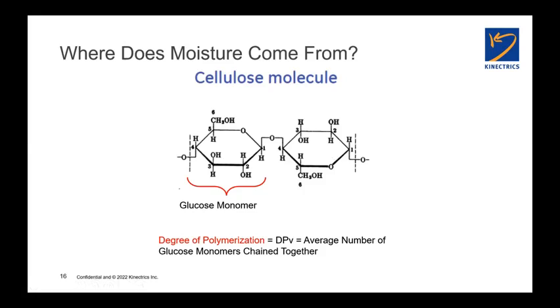And cellulose is the world's most common naturally occurring polymer. Normally when we talk about polymers, we're thinking about synthetic polymers, which are plastics. Cellulose is a natural polymer. And the number of these cellulose monomers that we have joined together is what we call the degree of polymerization. So right now on this picture, we have a degree of polymerization of 2, because I have 2 glucose monomers joined together. New paper, brand new, typically has a degree of polymerization somewhere between 1,000 and 1,200. End of life is deemed to be somewhere around 150 to 200. Different people make arguments for different numbers, but at a high level, those are the endpoints.